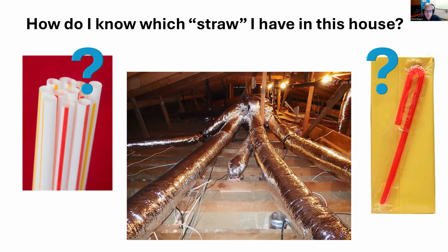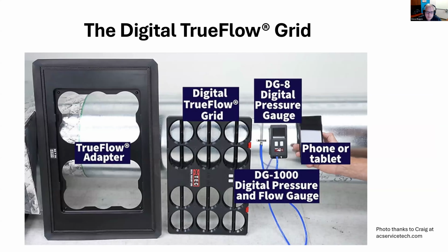So the way that we recommend is the digital TrueFlow grid. And I'm going to show you what this does. If you're not familiar with this product, this is becoming widely used and popular in retrofit processes, because by using this type of evaluation, HVAC contractors are able to predict whether they're going to have airflow problems with the new system or not before they sell the job.